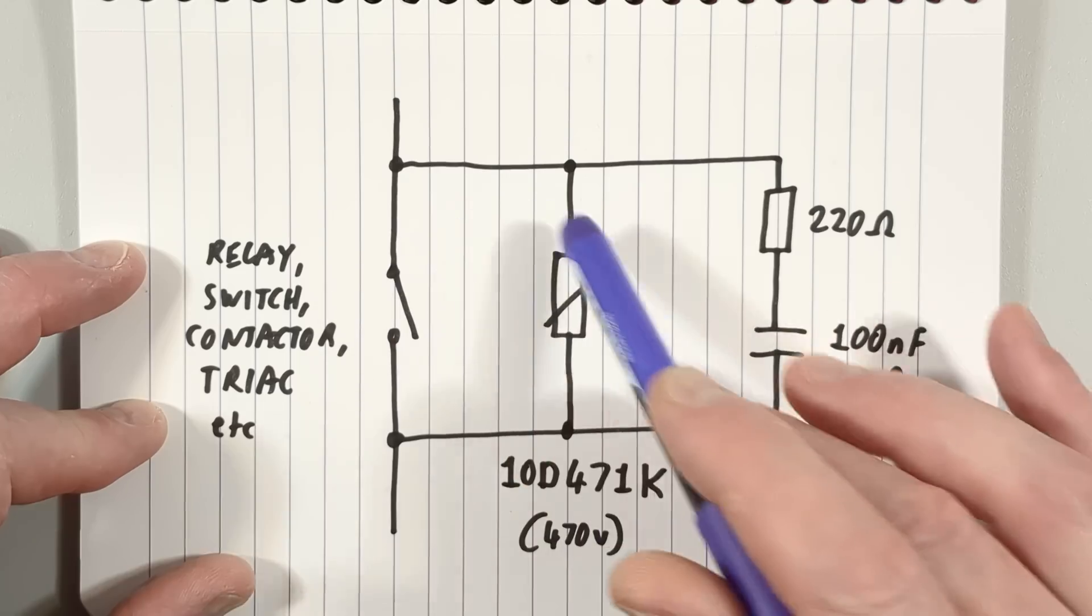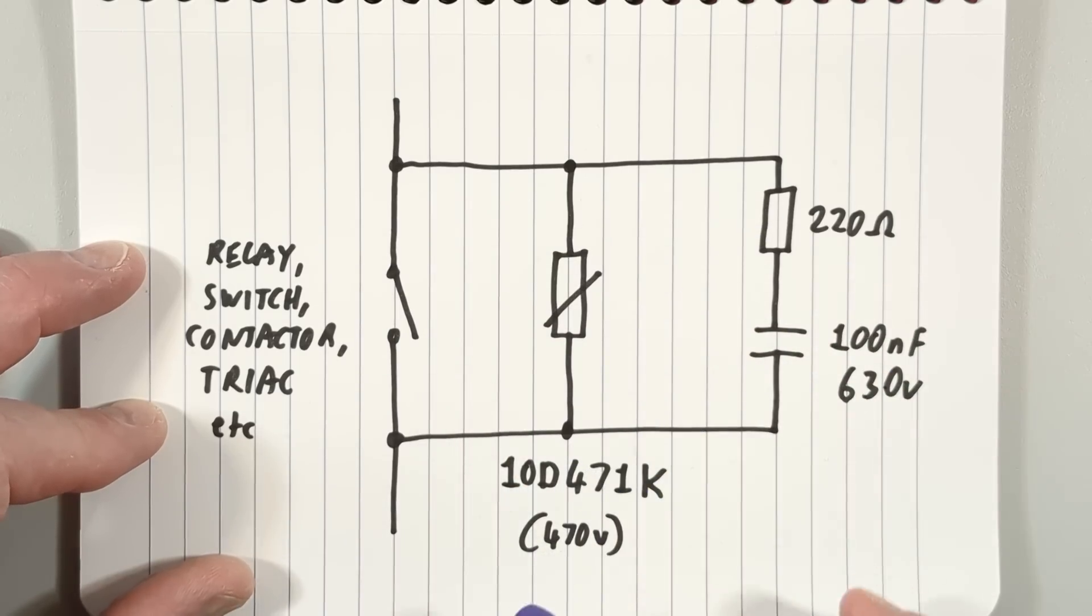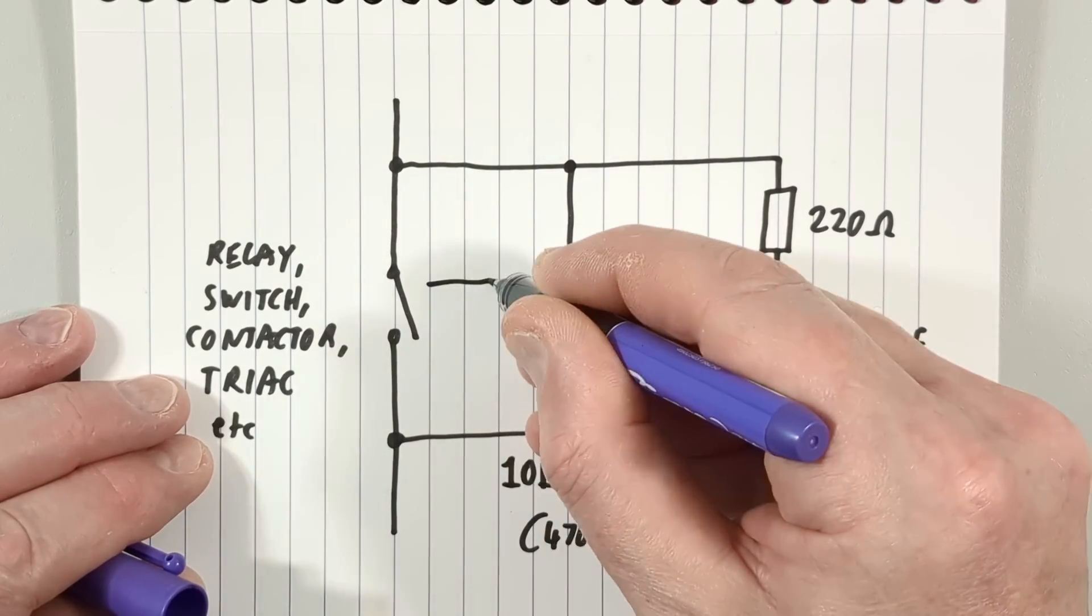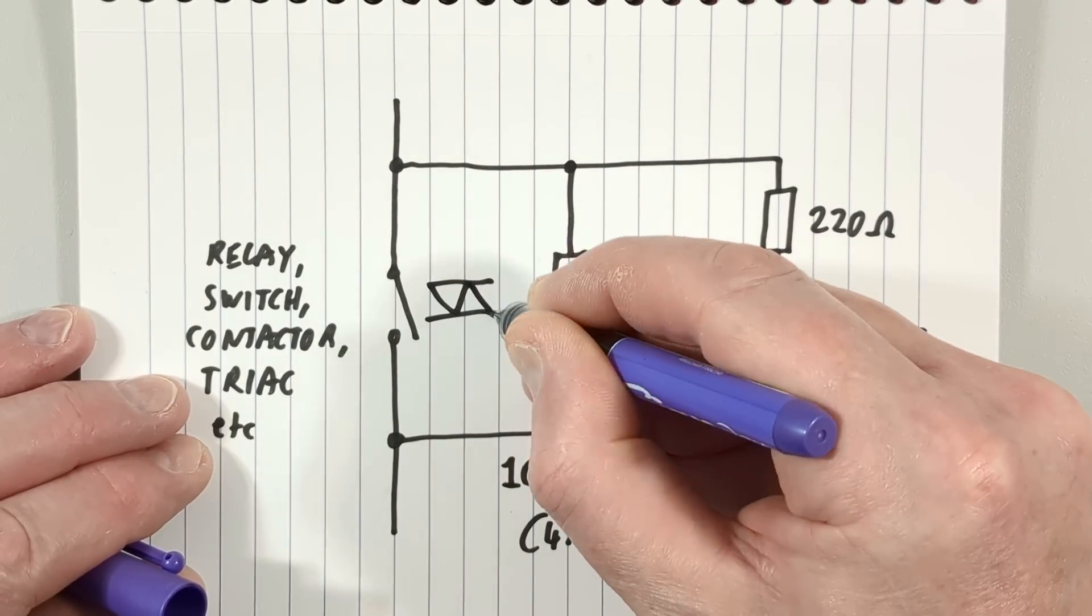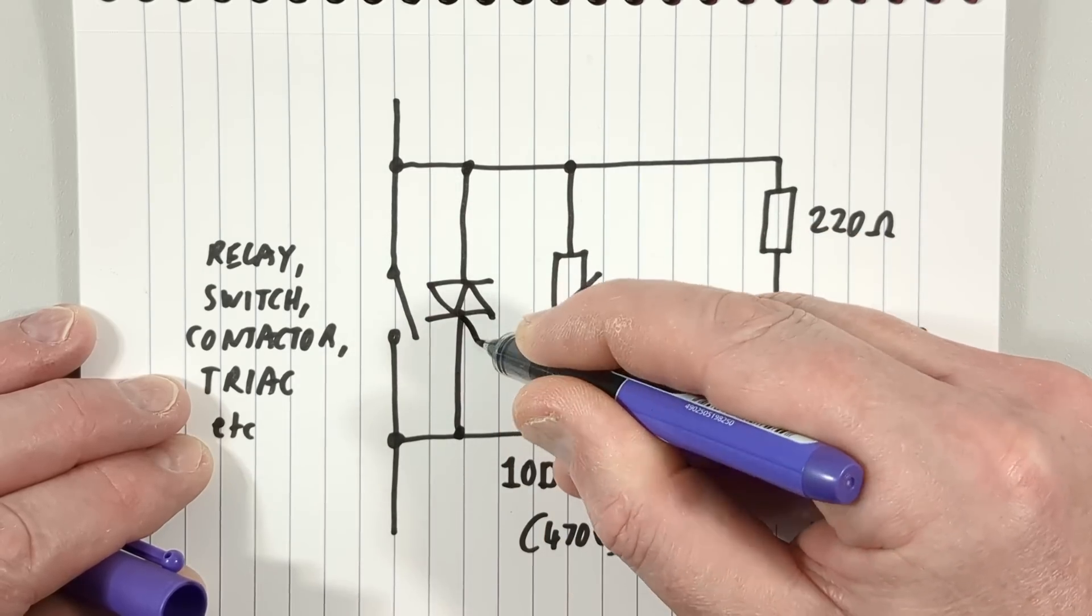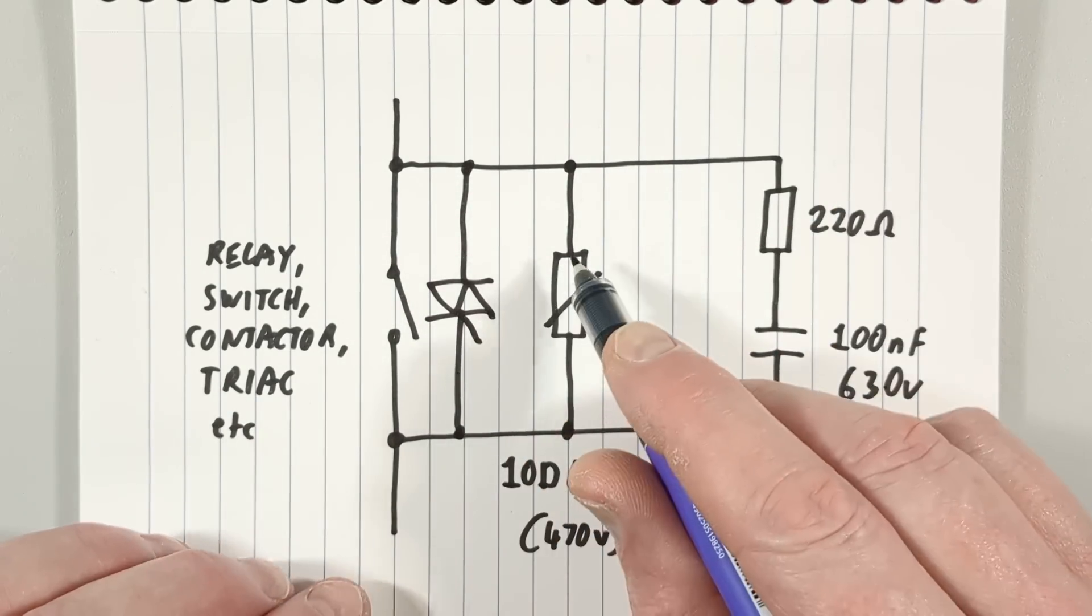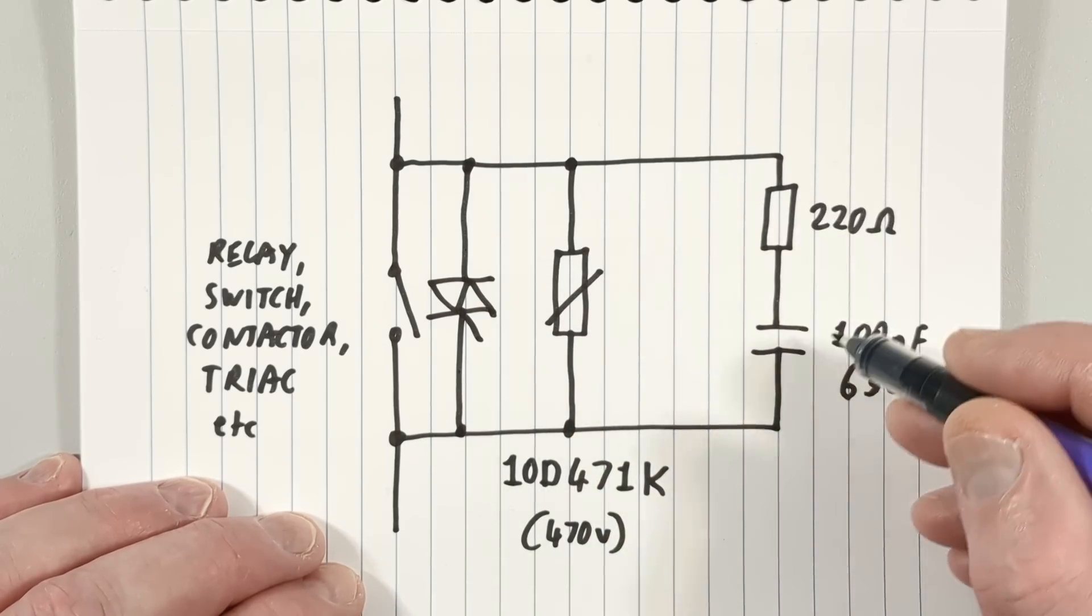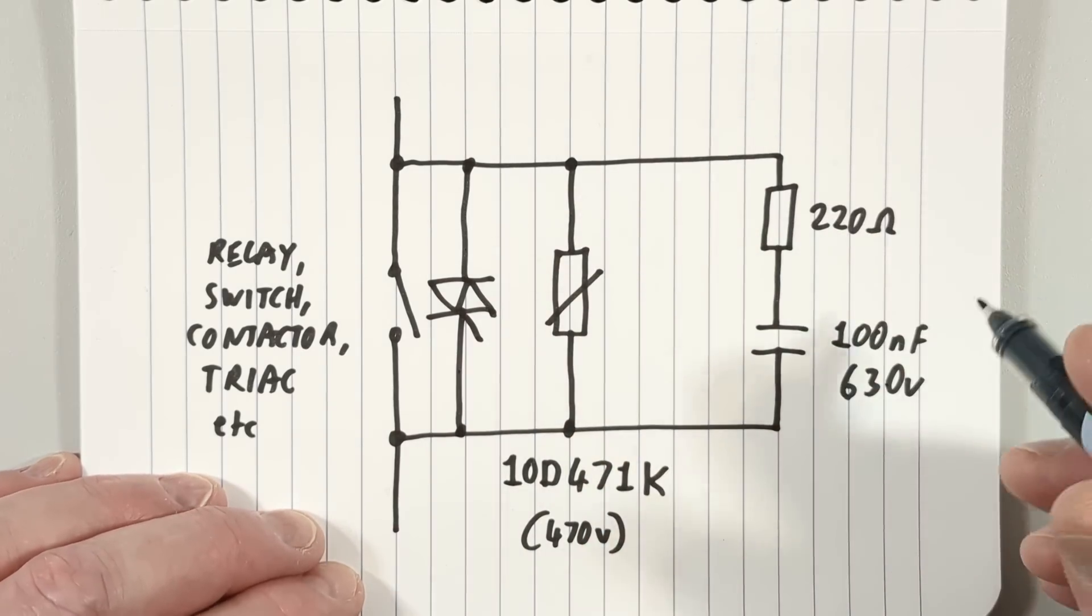These are also useful across things like triacs. When you've got a triac being used to switch loads, it's useful to clamp voltage spikes across it that could cause problems. That's what the metal oxide varistor can do, and the capacitor will also have that effect of clamping transient spikes.